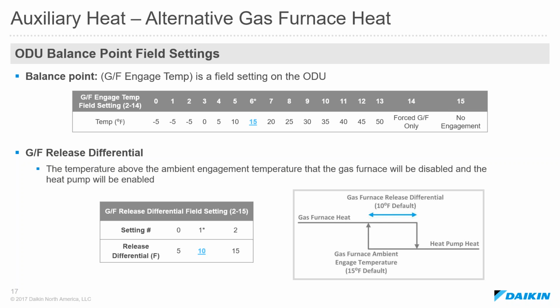Now we're telling the gas furnace when to come on. There's also a setting associated with when the gas furnace is going to shut off. The main objective of this setting is to avoid scenarios where the gas furnace is coming on and off and cycling. So by default, if it were to come on at 15 degrees, it's not going to shut off until 25 degrees outside. That can be set as low as 5 and as high as 15. And again, that's just to avoid having the gas furnace coming on at 15 degrees and then shutting off because it bumped up to 16 degrees. You want to avoid any sort of short cycling.